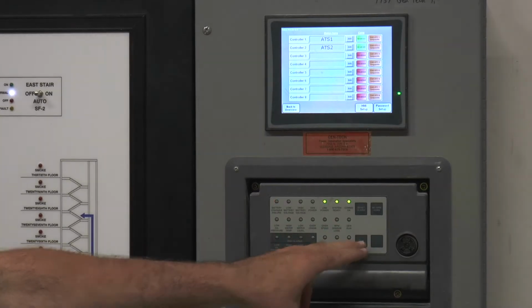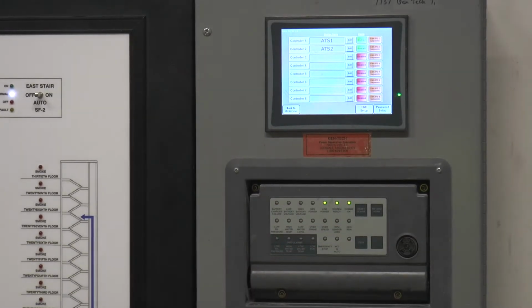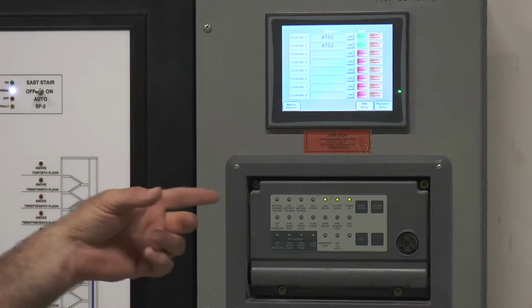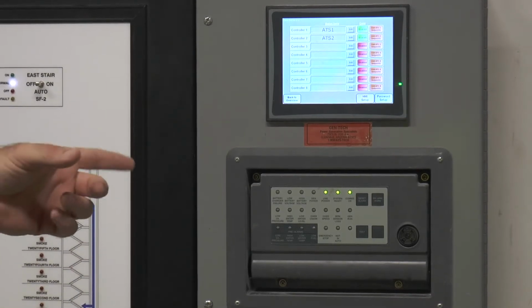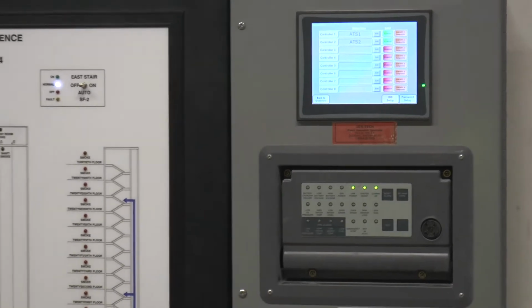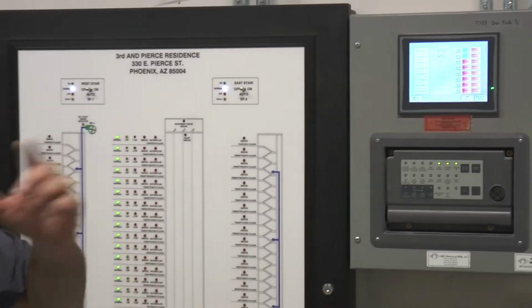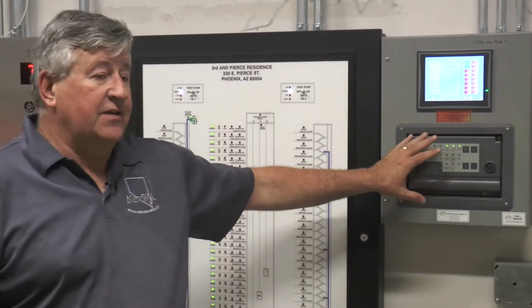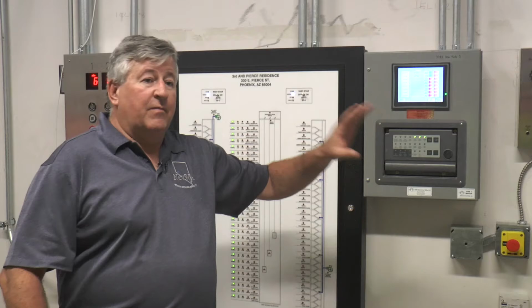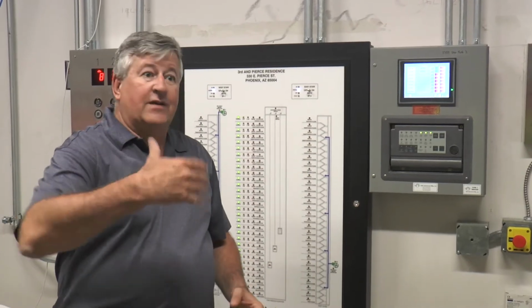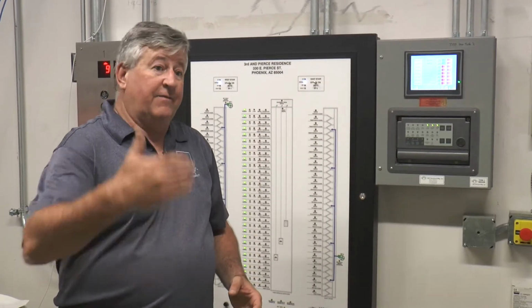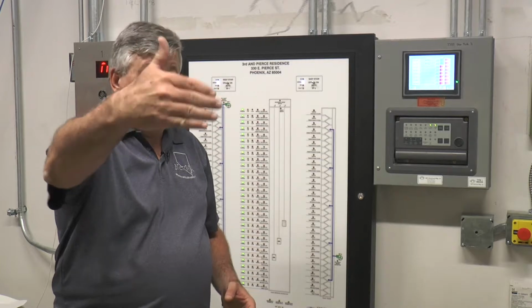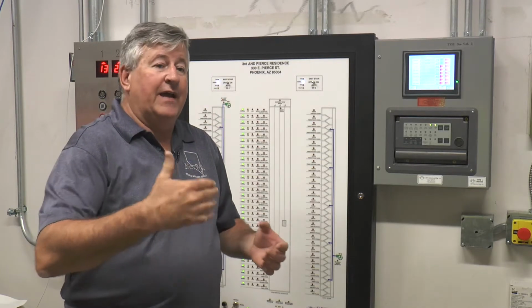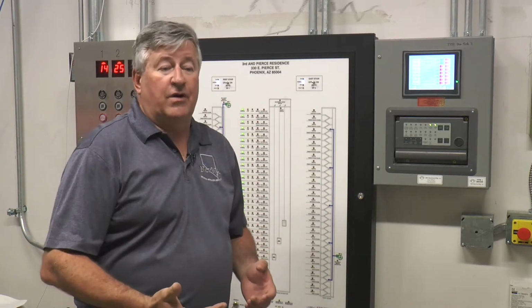You'll hear that. Since this room is unoccupied, it's probably going to be the responsibility of the front desk or security to notify you when there is a condition. The generator itself will also have an annunciation and an alarm locally. So I'm not sure where your office is located, if you're back by the equipment room in that area, or if you're walking by the louver, you may hear the horn going off in there also.